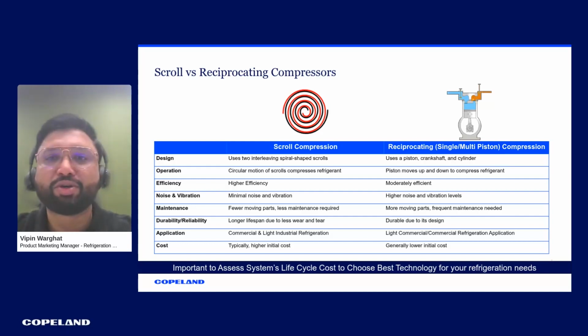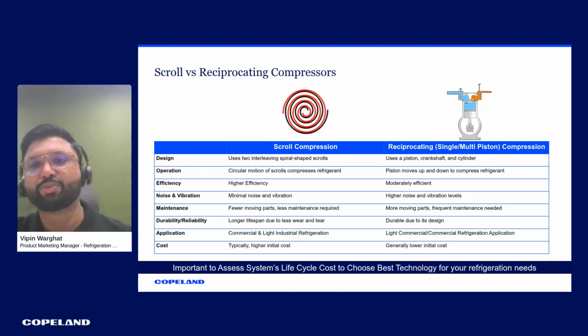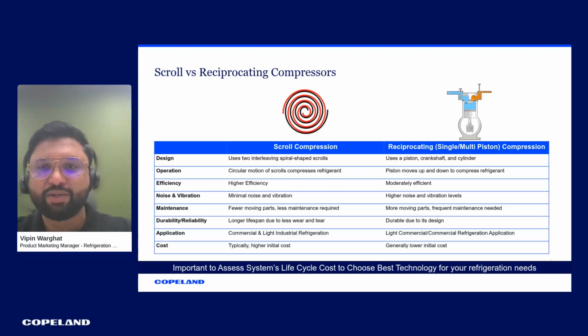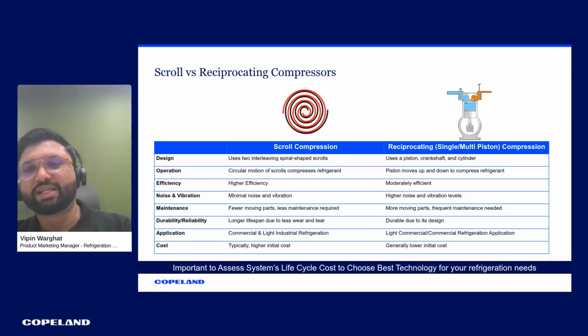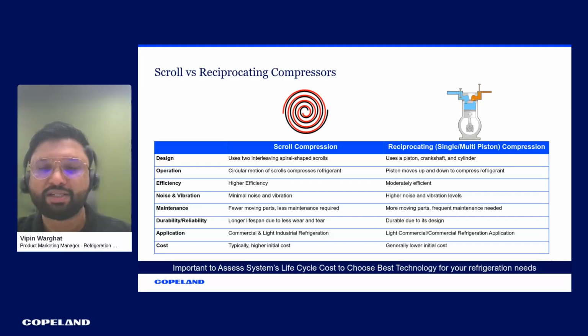So because of the scroll's higher volumetric efficiency, it delivers higher efficiency. Reciprocating or semi-hermetic relatively deliver a moderate level of efficiencies. Of course, there are some advantages around both technologies. However, it is really important to assess the best system for your cold chain requirement. It is important to assess the life cycle cost in order to choose the best technology for your cold chain requirement. So that assessment is important to do, and we will give you some examples today which will help you understand why it is really necessary. So if we go to the next one, Steve.